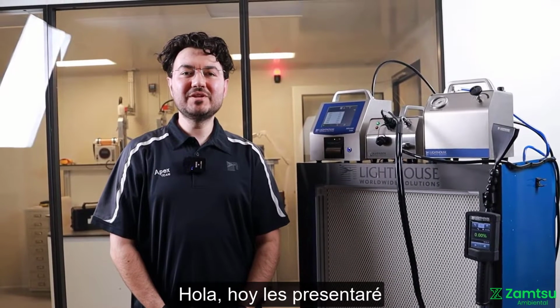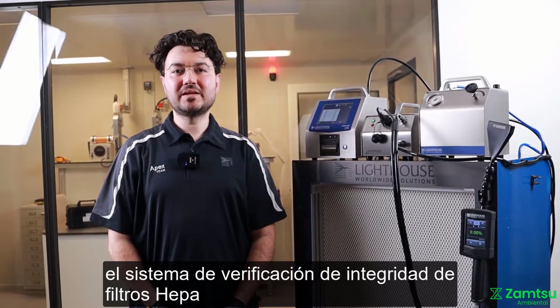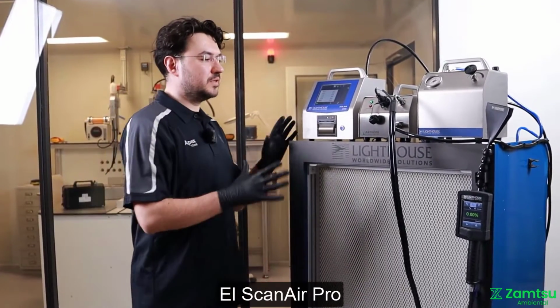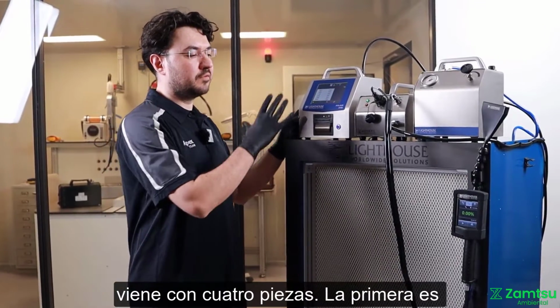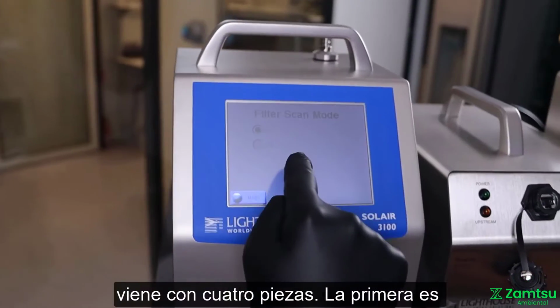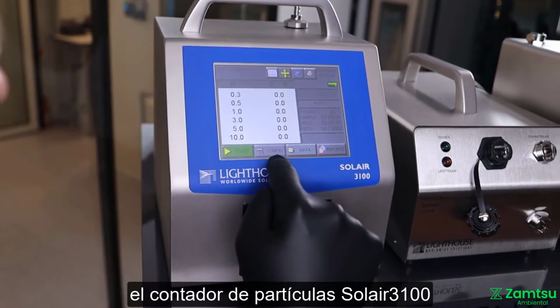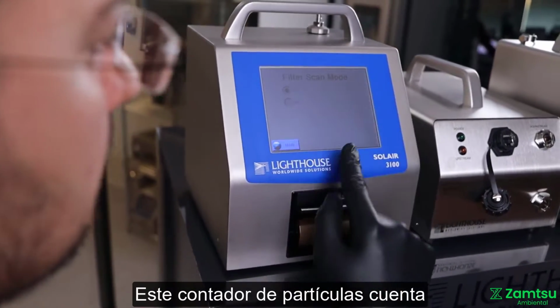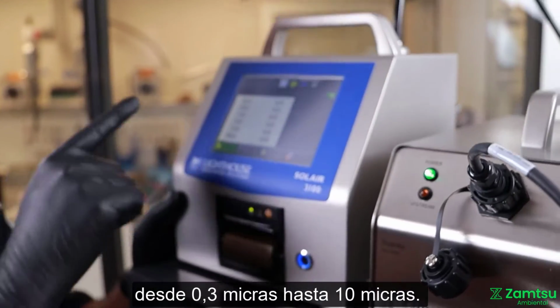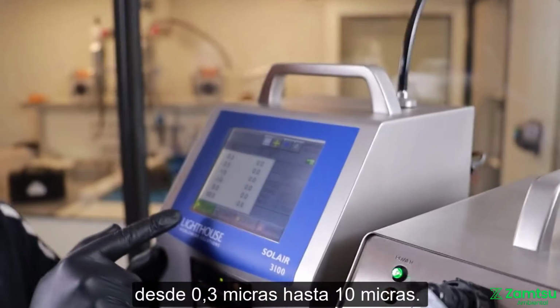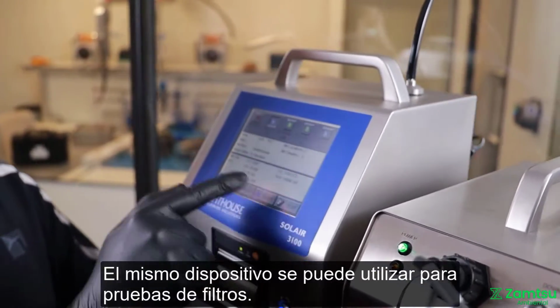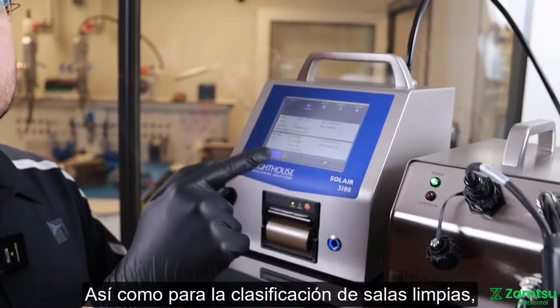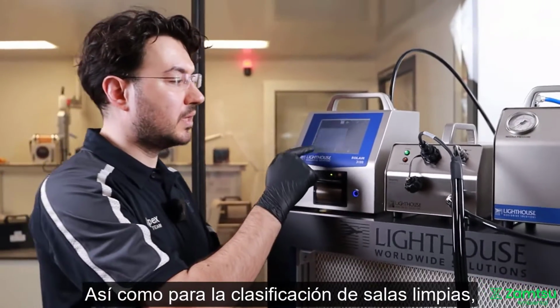Hello, today I will introduce you to ScanAir Pro filter testing equipment. Lighthouse filter testing equipment comes with 4 pieces. First one is the Lighthouse Solair 3100 particle counter. This particle counter counts from 0.3 micron up to 10 micron. Same device can be used for filter testing as well as for cleanroom classification.